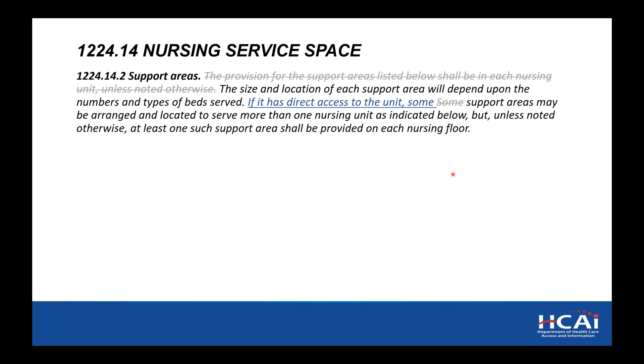In 2016, they put in a provision that all support areas for a nursing unit must be within that unit. We found that to be very restrictive for most facilities. So we've removed that requirement, but added if it is, they must still have direct access to the unit. So if you have parallel nursing units with a nourishment room, soil utility, clean utility, equipment room in between the two, as long as they have a door going into each unit, that is fine. That was causing a lot of unnecessary hardship on a lot of facilities. We're going to look at some of those examples here.